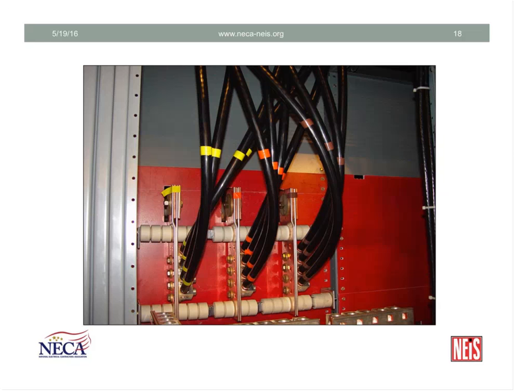This is a look inside the back of a switchboard, a fairly large switchboard, with some large conductors—4 conductors per phase in parallel that had to be terminated within this equipment. A quality aspect of this installation is the alignment of the conduit entries into the top of the enclosure. If the installer didn't enter the enclosure in the right position, they would not have been able to dress this termination as you see in the photo without putting undue stress on the conductors.